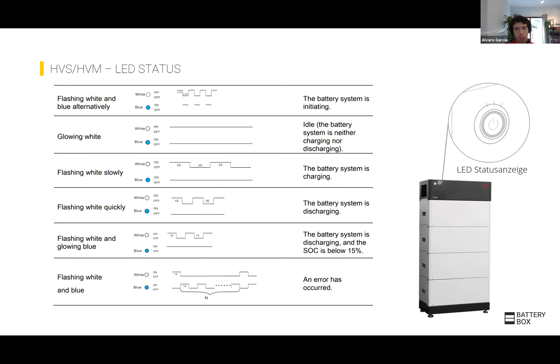And as a final step, when you extend a high voltage system, or if you had an issue and you had to replace one of the modules, take into account that the batteries, when they come from the factory, they come at 30%. And these are batteries that are connected in series. So in order to allow them to balance each other and be able to charge and discharge at the same rate and be all at the same state of charge, you need to add the new battery when the old system is already at 30%.